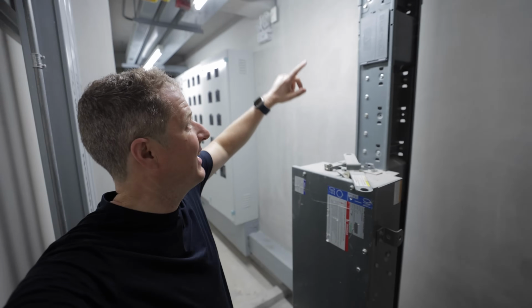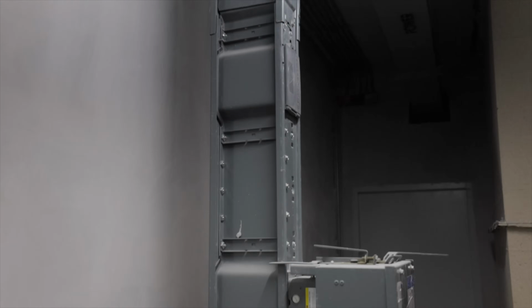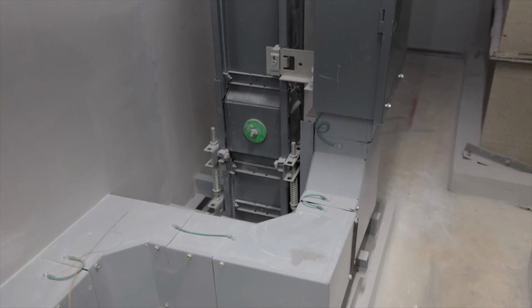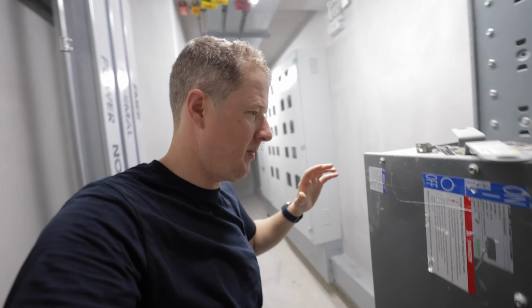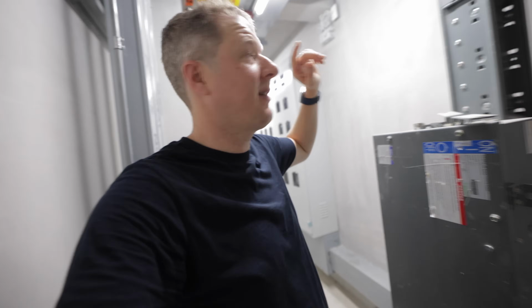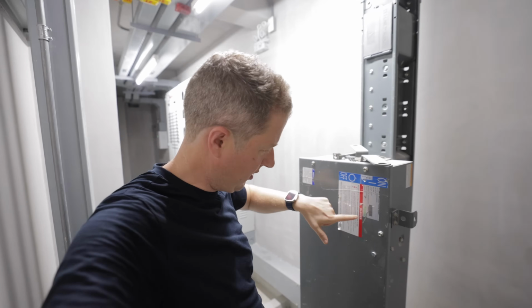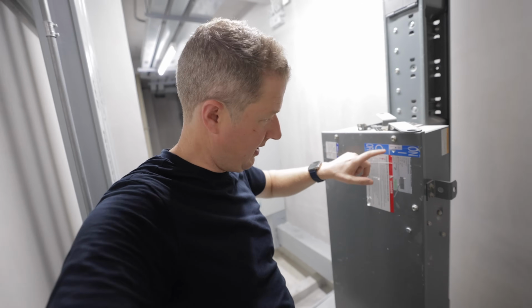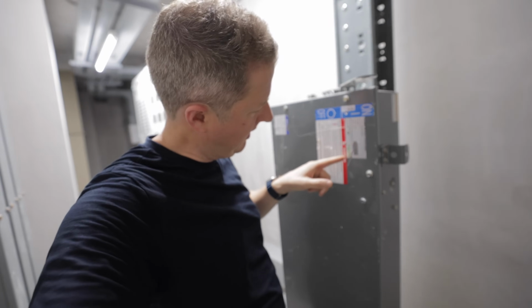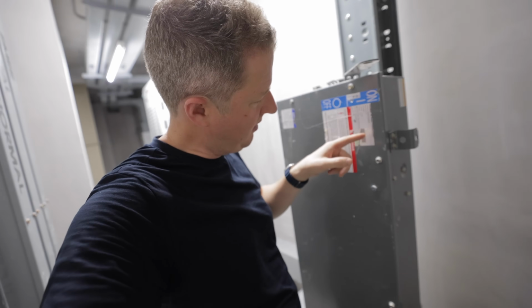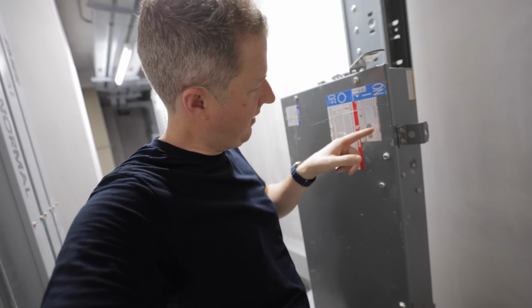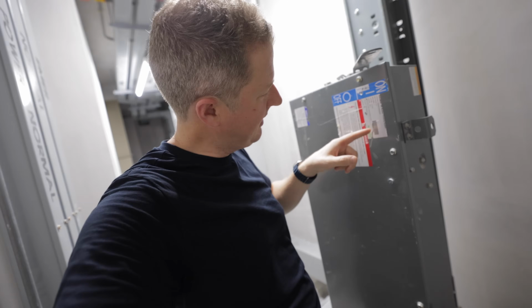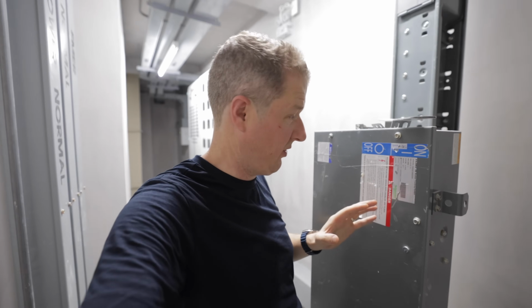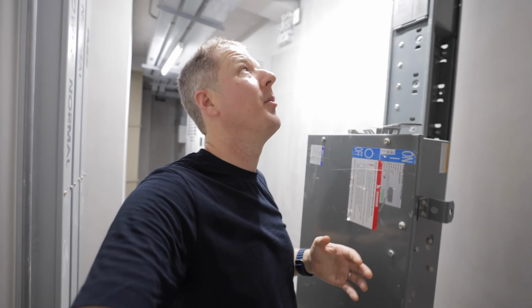So this is a D-line busway, right? It's actually D-I Line 2. D-line I am familiar with, it's one of the few things that's not foreign to me here. They make big heavy equipment. In fact, I think D-line got bought out by Schneider Electric, so that's why you can see on here, this is actually a Schneider Electric label. So it's a D-line 2 bus bar trunking system, 415 volts, 3-phase neutral and earth, rated at 2000 amps, which sounds about right for a building that's got nearly 1,000 apartments in it.